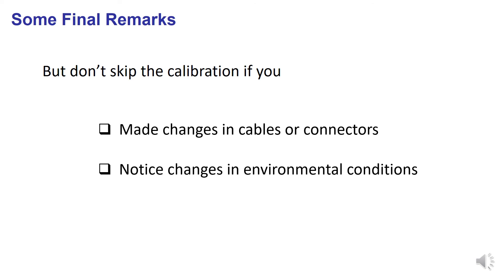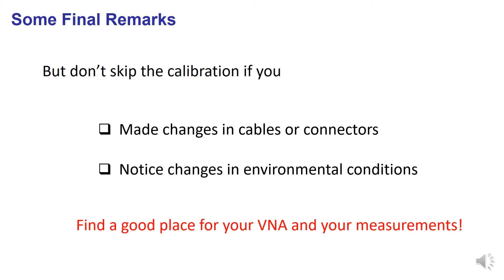You might want to enlarge the time at which your calibration remains valid by reserving for your instrument an open and well-ventilated place in a laboratory free of dust and with low temperature drifts.